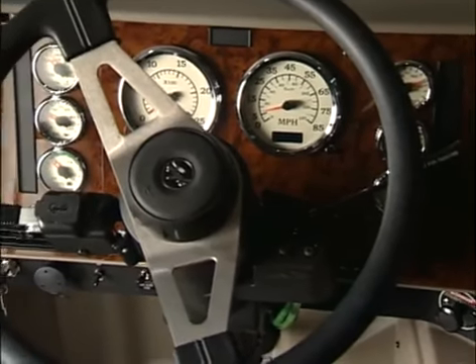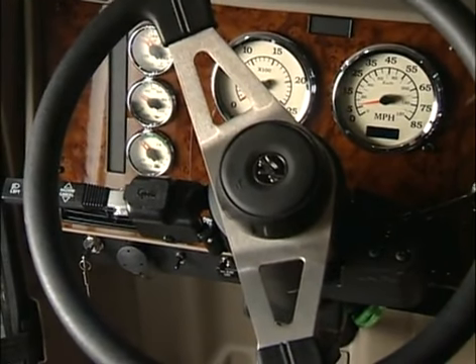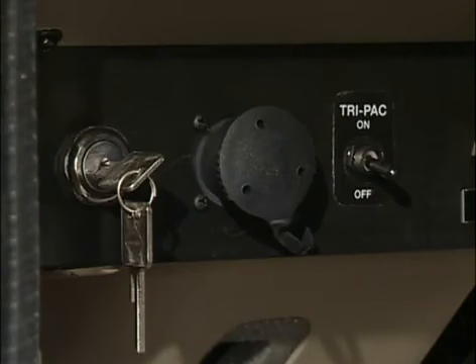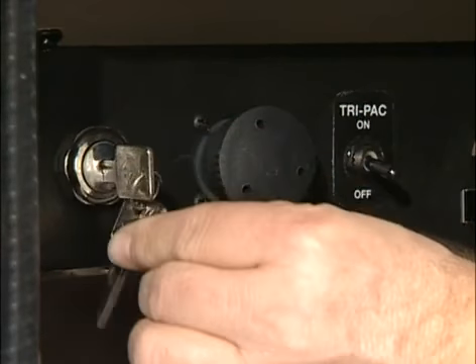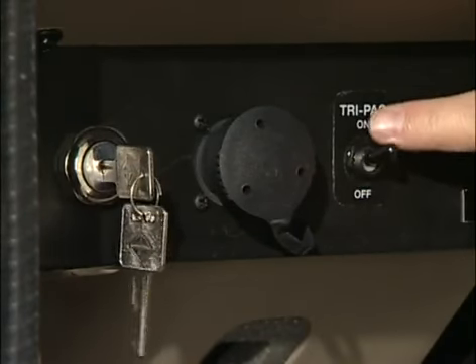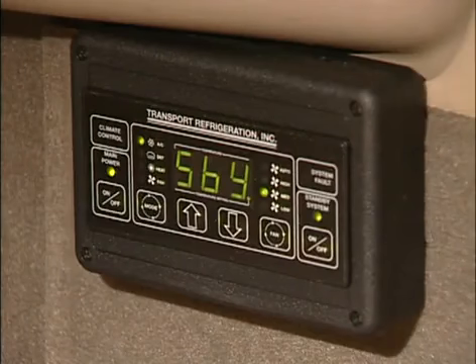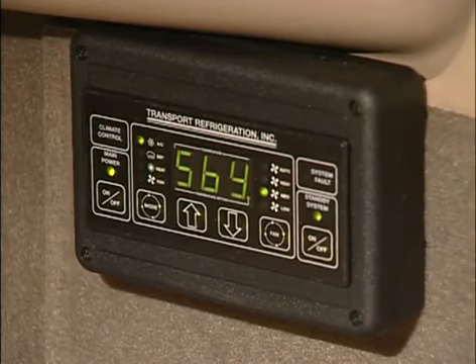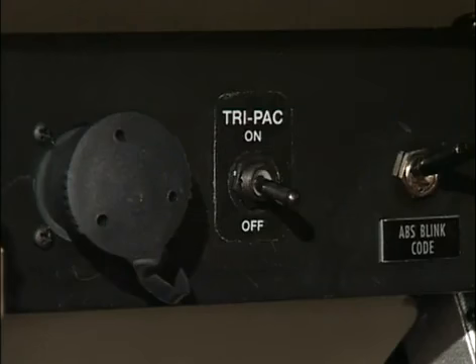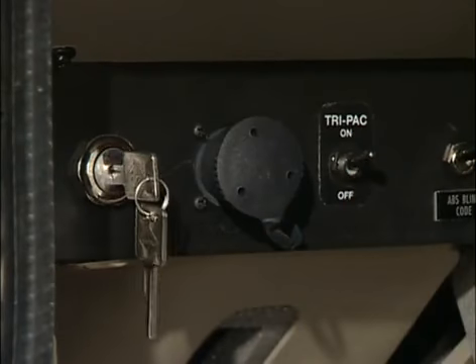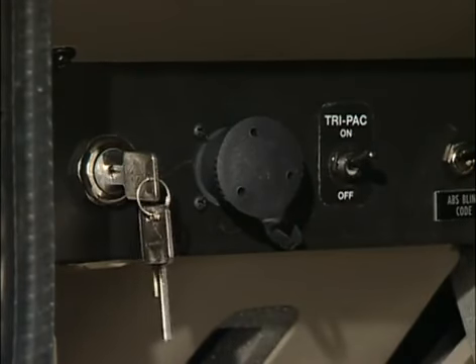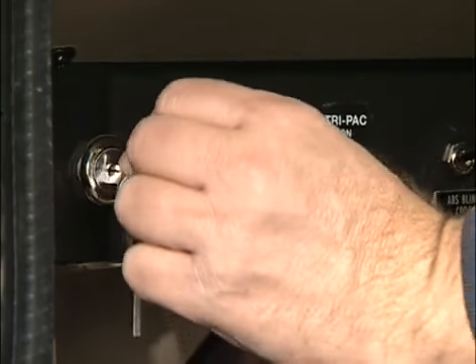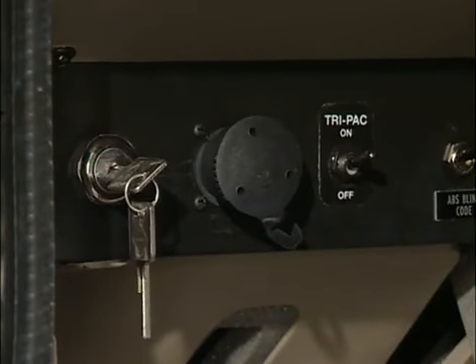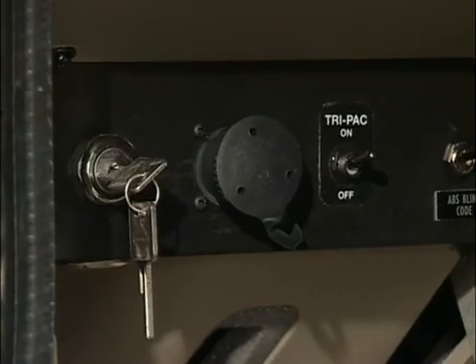One of the TriPac features that improves driver acceptance and system use is a dash-mounted selector switch. When the tractor ignition is turned off, the driver can manually turn the system on or off, forcing the controller to standby mode. The selector also allows the system to be integrated with the tractor's ignition. Whenever the tractor's ignition switch is in the off or accessory position, the unit will operate normally. If the tractor's ignition switch is in the start or ignition position, the controller is forced to standby mode, turning off the system.